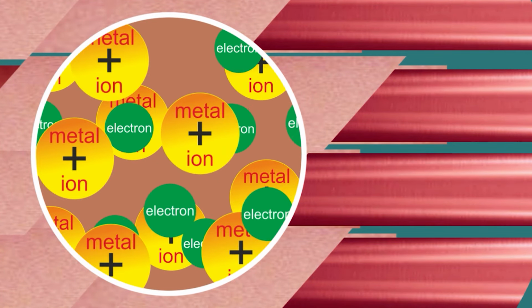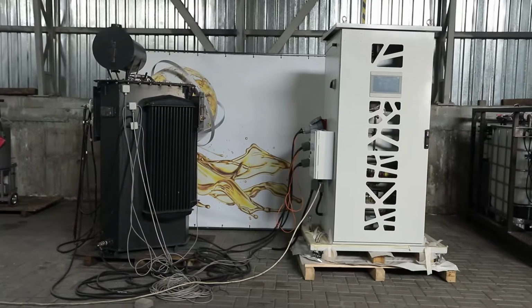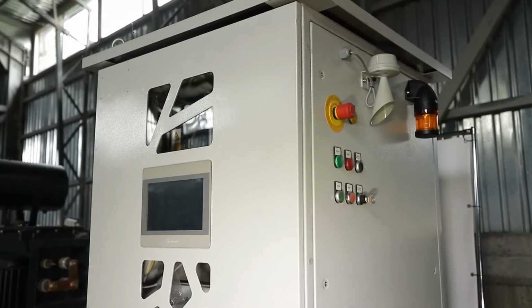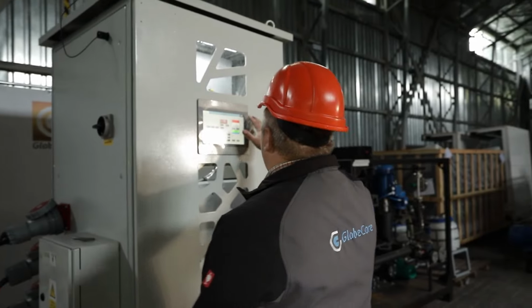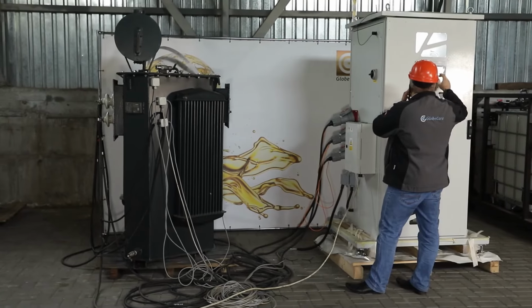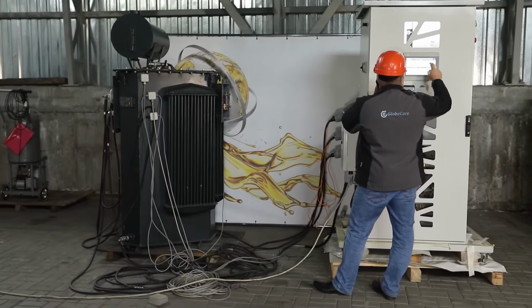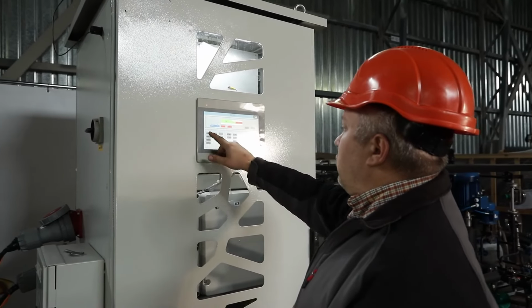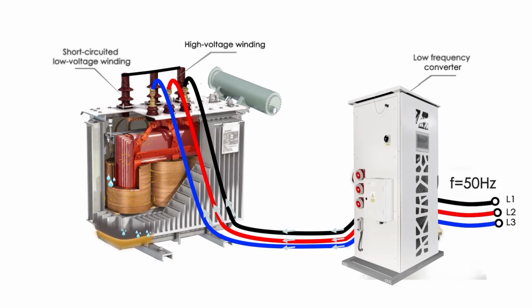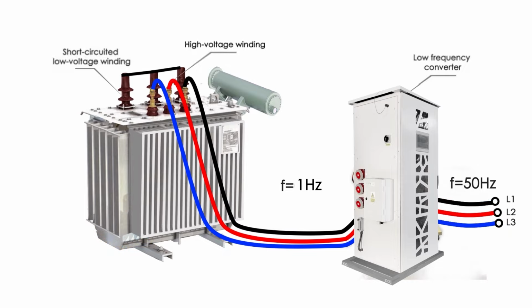from the winding insulation. In order to put this method into practice, we need to use a frequency converter to convert the network 3-phase current with a frequency of 50 or 60 Hz into a 3-phase current with a frequency of 1 Hz. In this case, the value of the amplitude of the converted current should not exceed the nominal value of the current for the high voltage winding. Further, the current of already low frequency is supplied to the high voltage windings of the disconnected transformer, while the low voltage windings are short-circuited.